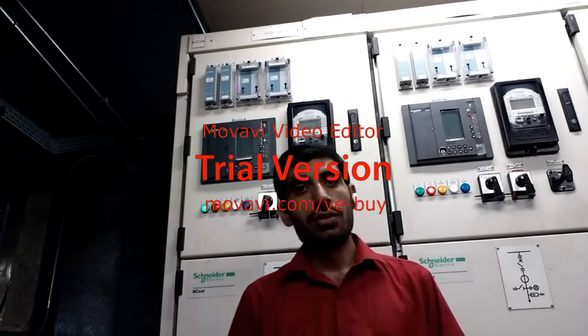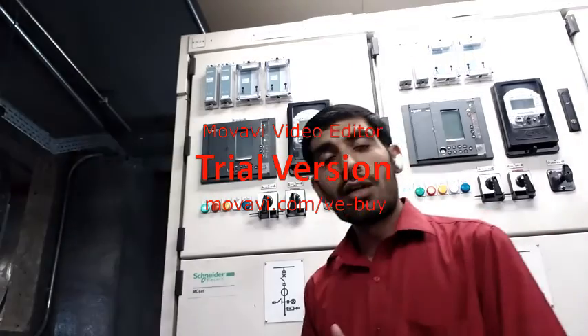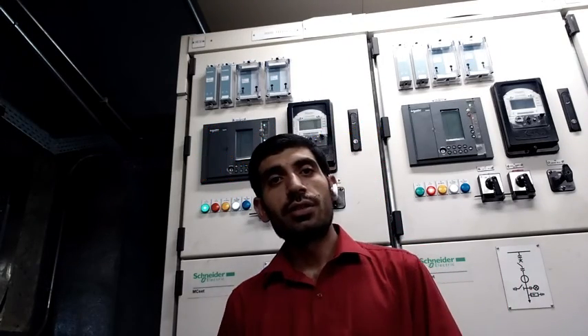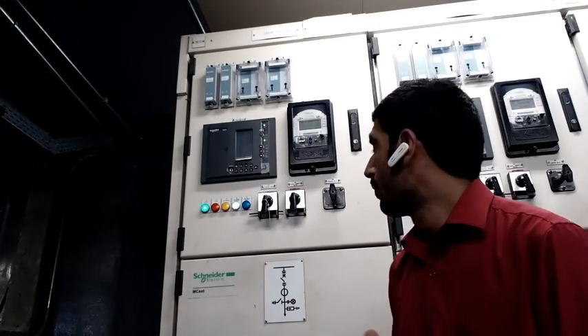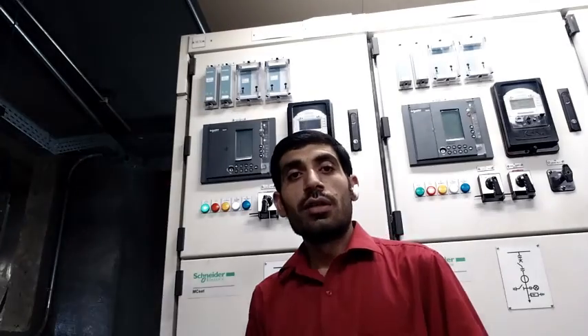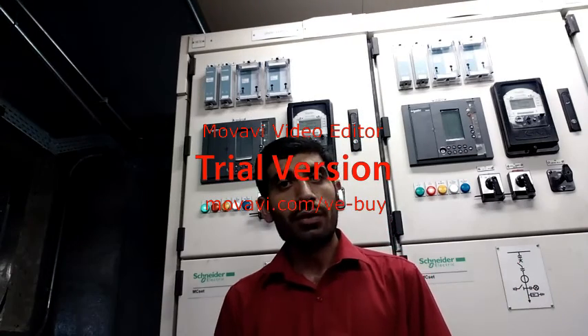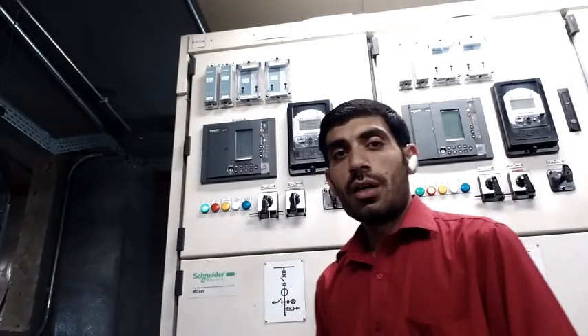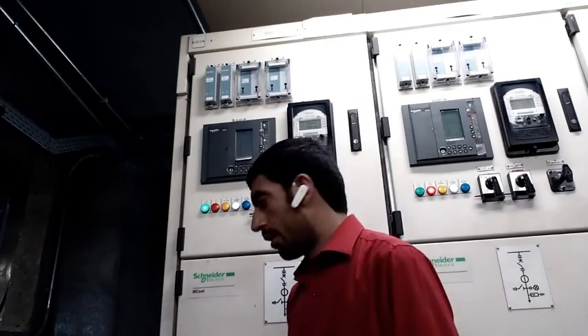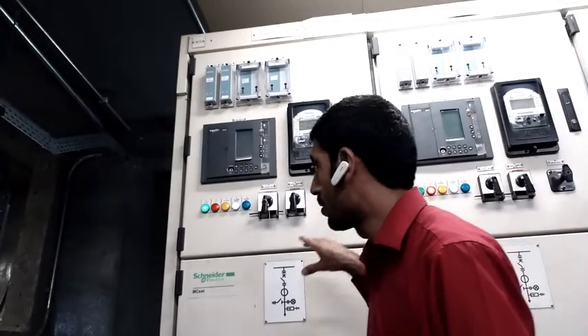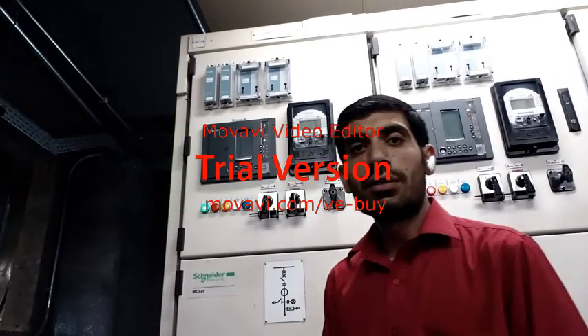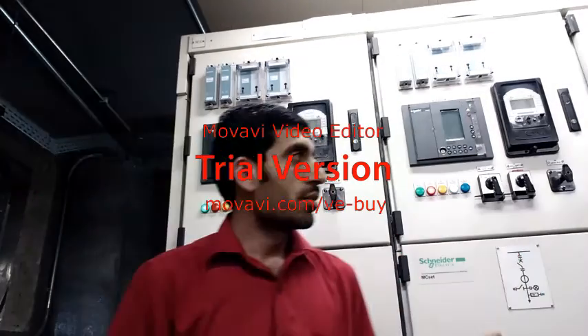This is an electronic multifunction meter, that's why we cannot inject more voltage, because this is a small device and our voltage is high and also our current is high. That's why we use VTs and CTs for these multifunction meters and for protection relays, for low values. So we have a step down transformer for VTs and also a step down transformer for CTs. The CTs are connected with the bus bar, this feeder's CTs are at the back side of the feeder connected with the bus, and the VTs come from the bus metering.